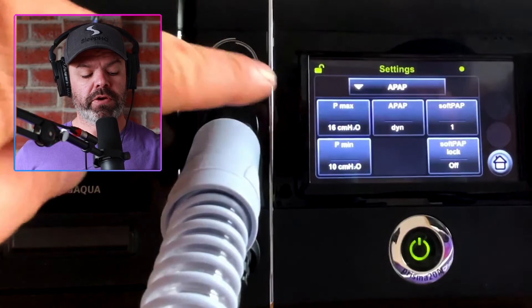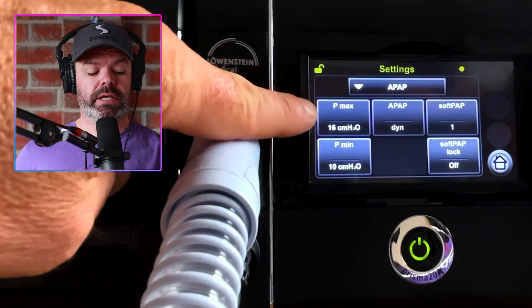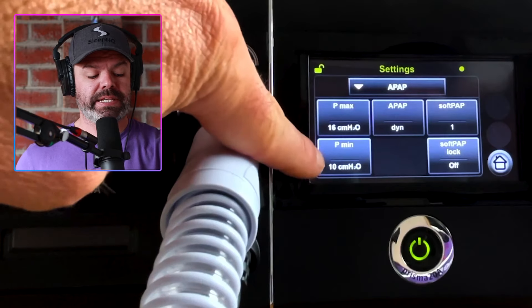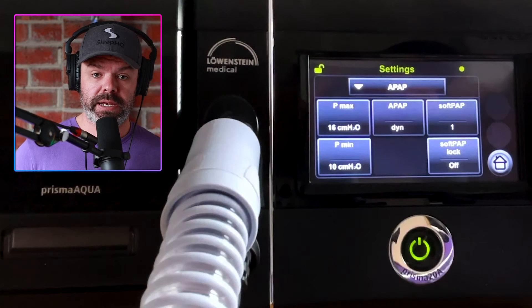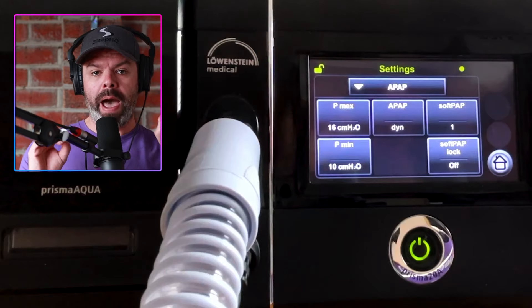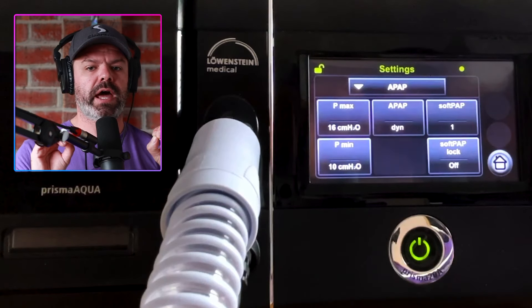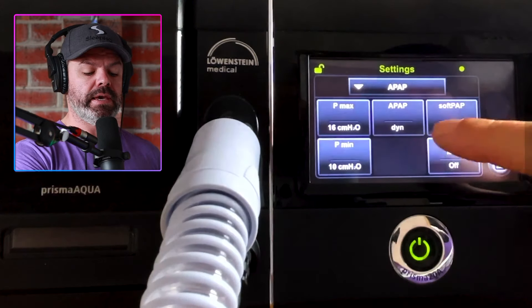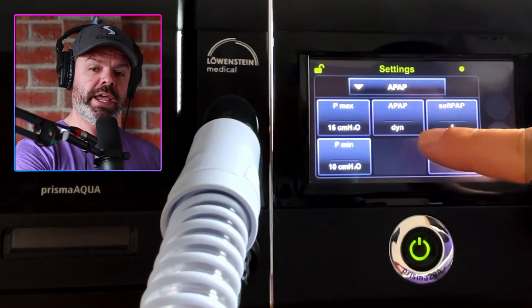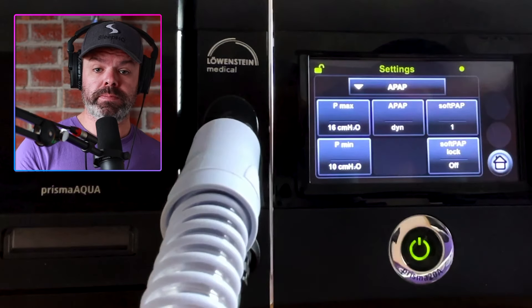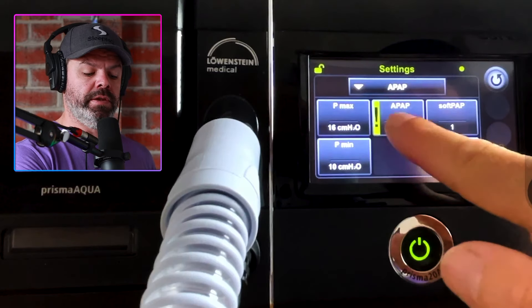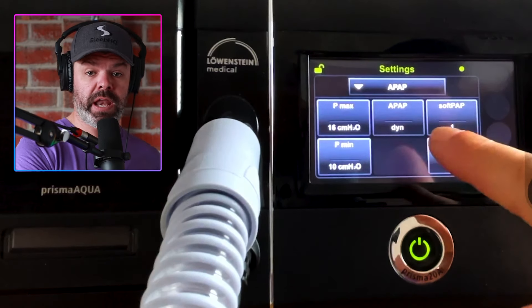Over here on the left we have our pressure max and pressure min levels. Currently pressure min is at 10 and pressure max at 16 — this is the therapy range the auto algorithm will only work inside. In the middle we can change the algorithm response: standard and dynamic.